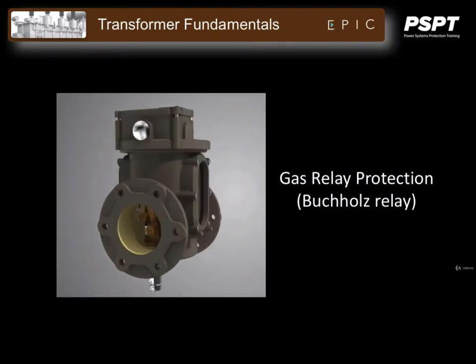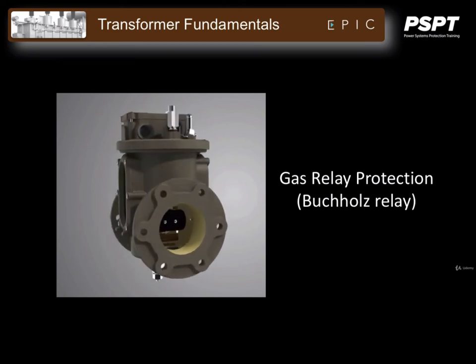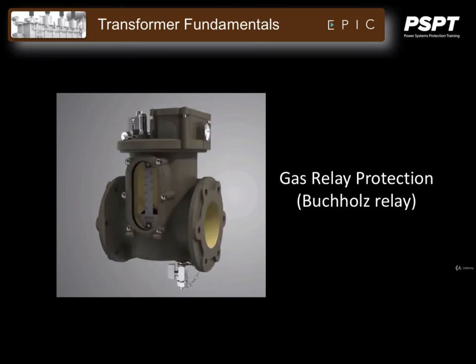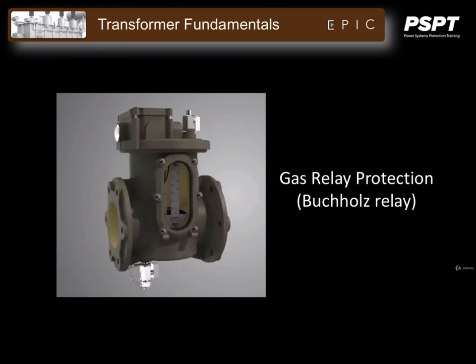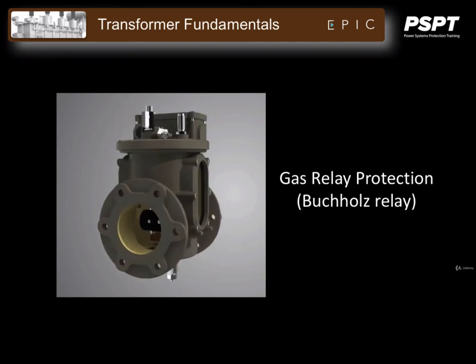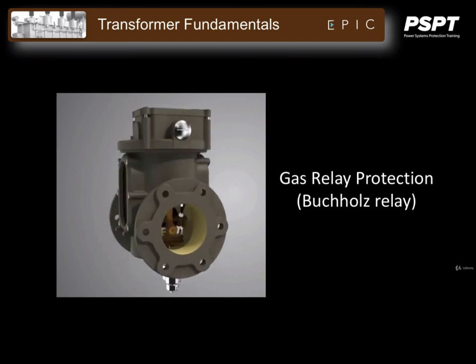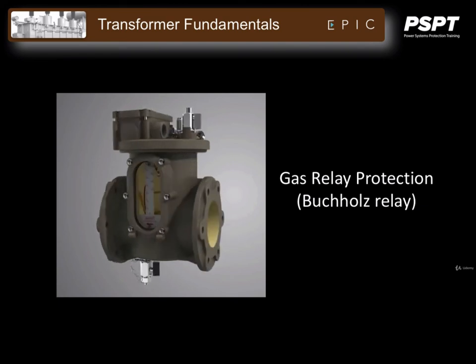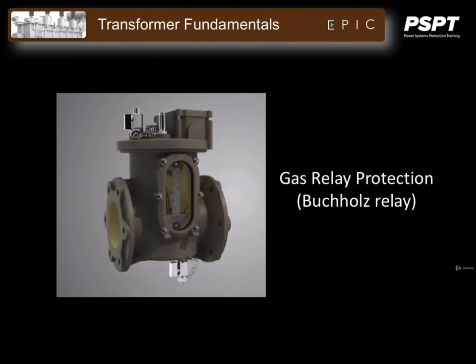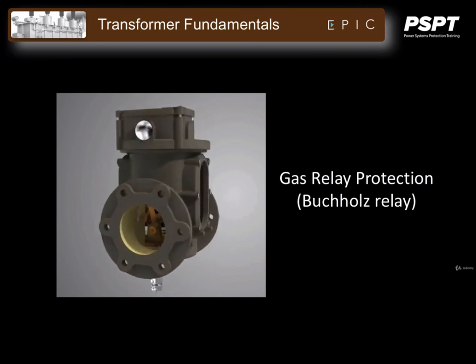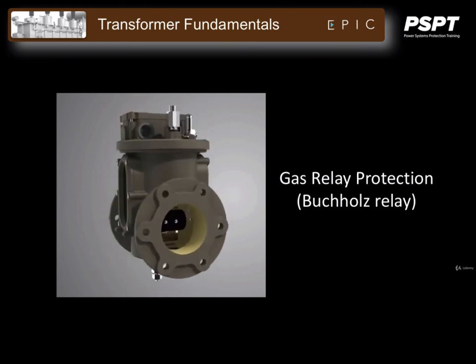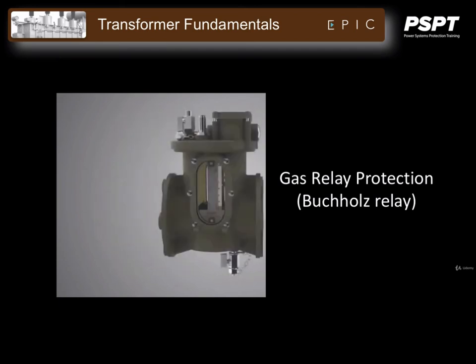The last protection device to be discussed in this chapter is more mechanical than electrical. At least the initiating variables, pressure and flow, are measured mechanically. This relay measures the rate and volume of gas accumulation in an oil-immersed transformer. It was developed by Max Buchholz in 1921 and since has been known as the Buchholz relay, which has been applied to large power transformers since about 1940. It has been slightly modified over the years, but essentially the basic principle of operation has remained unaltered.